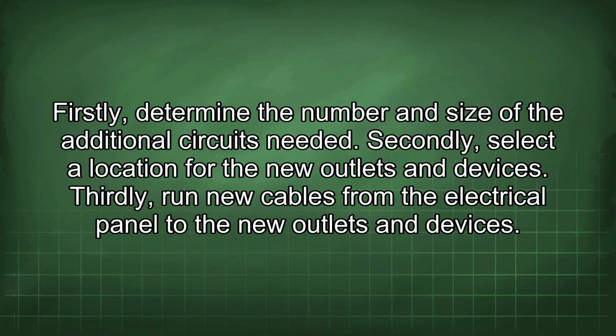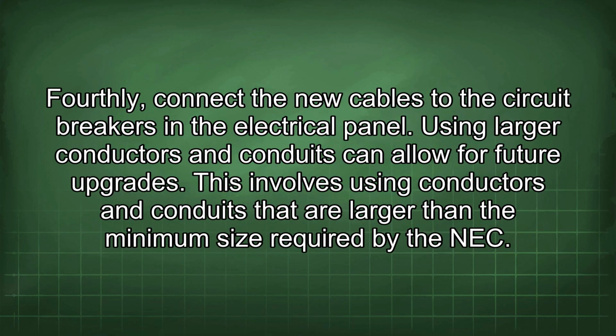Firstly, determine the number and size of the additional circuits needed. Secondly, select a location for the new outlets and devices. Thirdly, run new cables from the electrical panel to the new outlets and devices. Fourthly, connect the new cables to the circuit breakers in the electrical panel. Using larger conductors and conduits can allow for future upgrades. This involves using conductors and conduits that are larger than the minimum size required by the NEC.